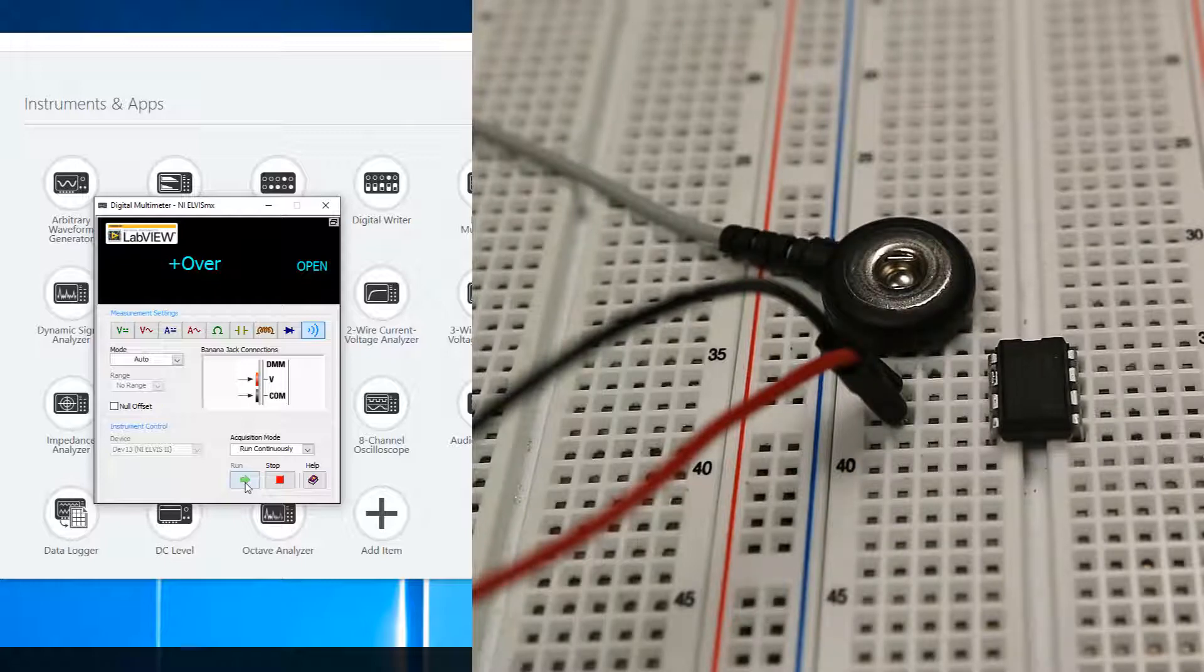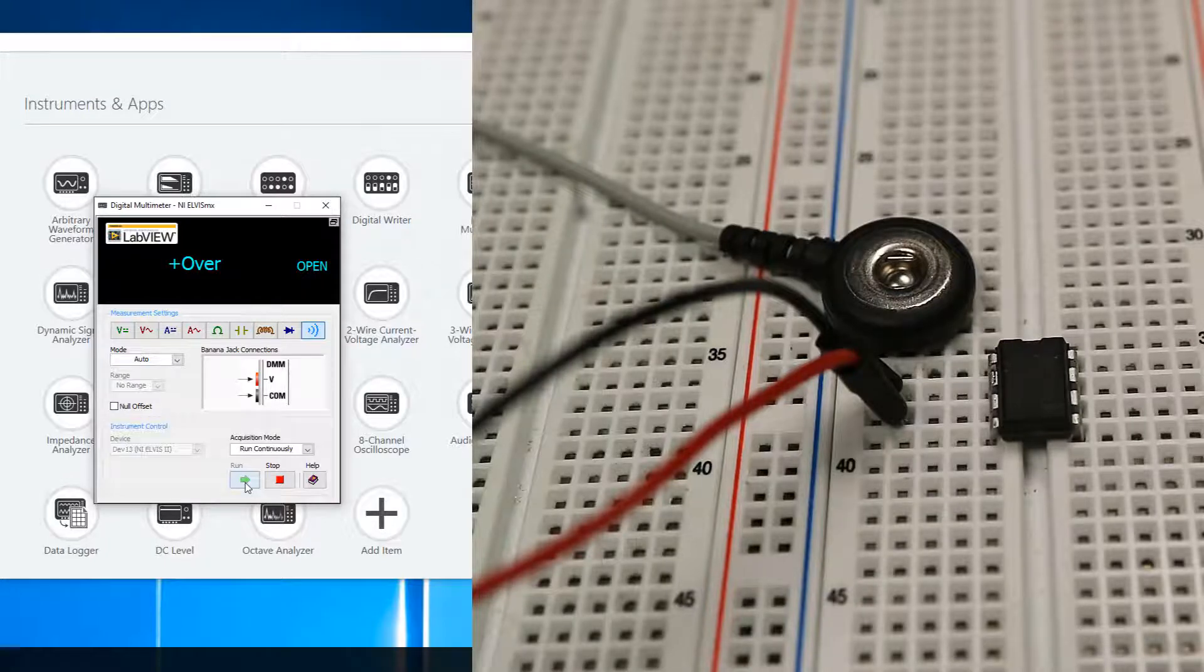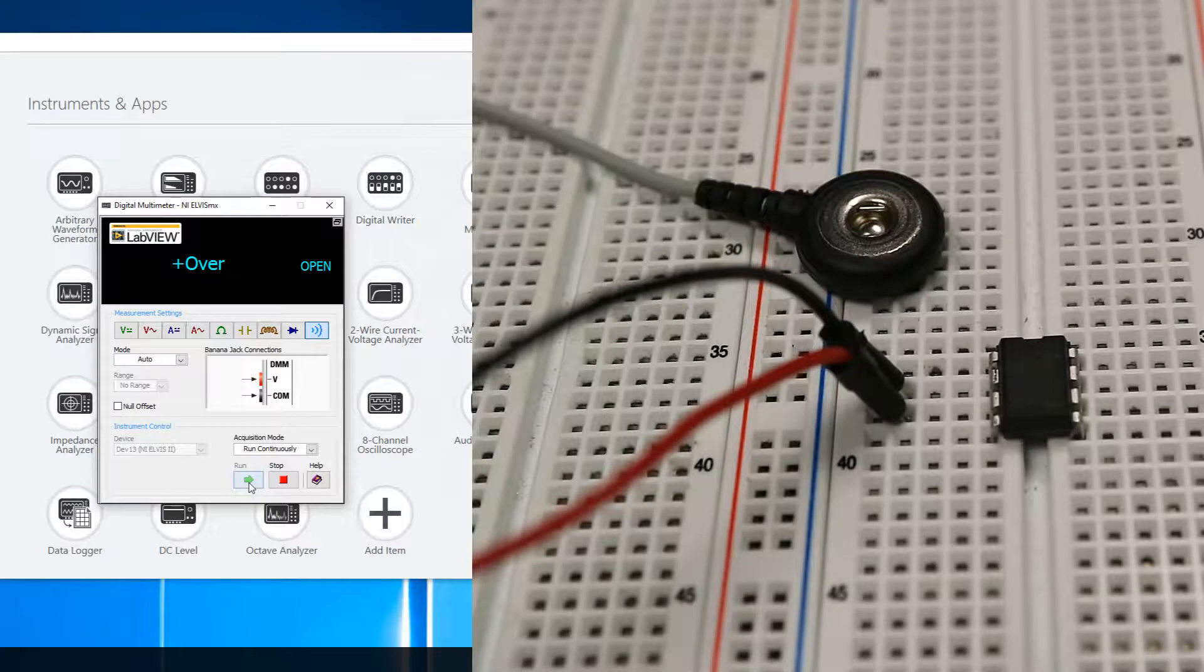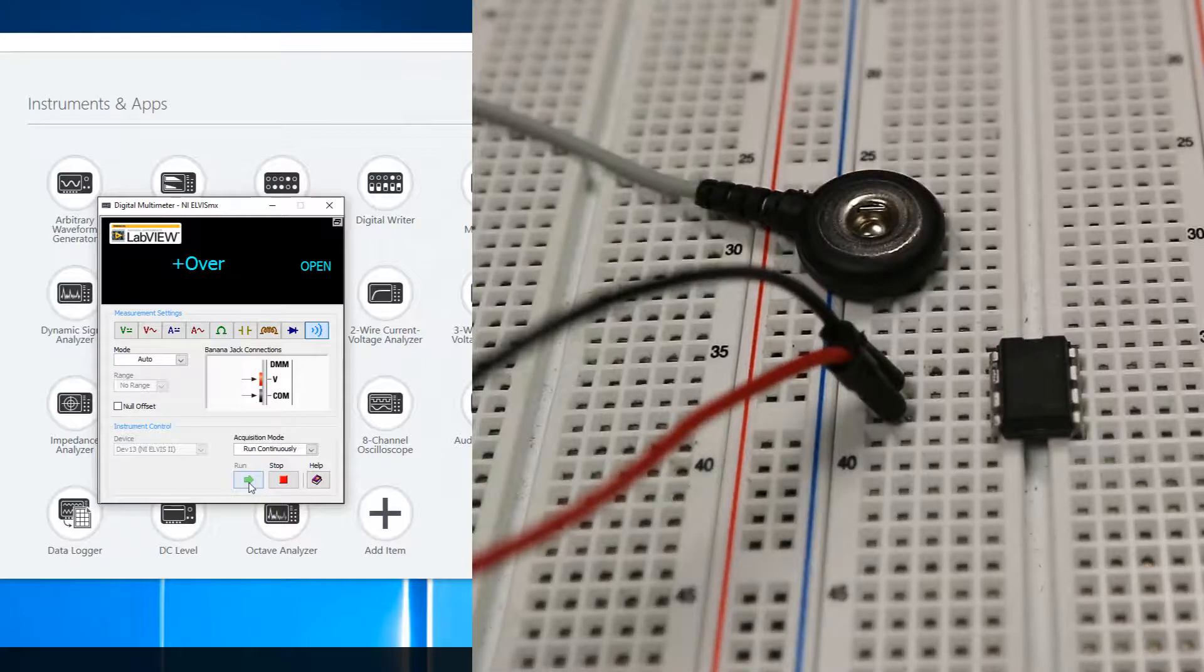Sometimes I have found that you just won't get a signal and you're trying to figure out why. Unfortunately, it could be a number of issues. It could be with the electrodes. I also found you can have problems with the hookup wires themselves. Some of them just don't work for whatever reason. So you can test those with the continuity tester.